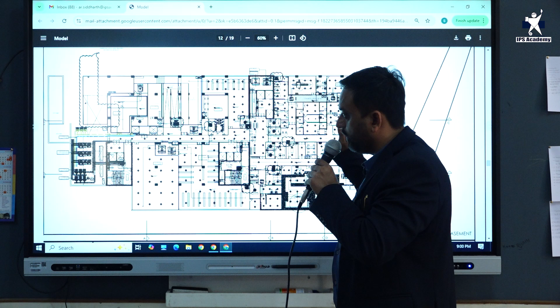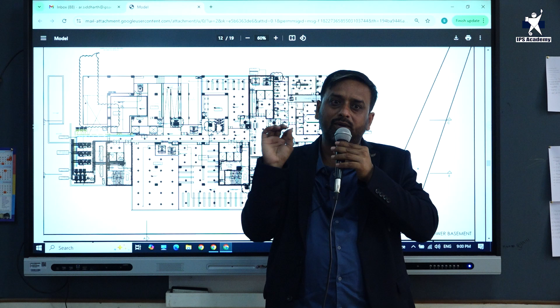So coming to the firefighting pumps, there are 5 types of pumps. Actually the building is getting protected in the firefighting system by 2 ways. A sprinkler system, which is your local protection, and a hydrant system, which is required in case of larger fire. So if there is a fire, your sprinkler can help you out. If the fire has gone huge, you need to go to your fire hydrant cabinet and open the landing valves. So hydrant and sprinkler, and third is external hydrant, which is a must. So in these 3 ways it is divided. So 6 inch pipes for such a building is enough. A 6 inch MS pipe or GI pipe can cater to the entire building.